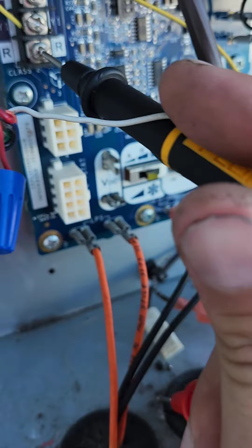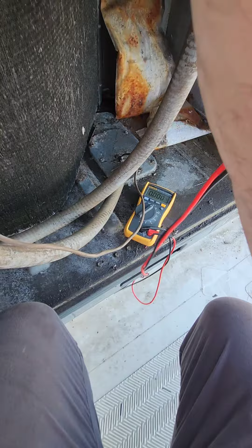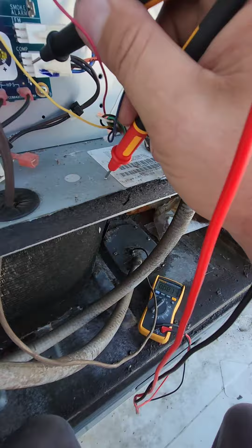Started checking everything else out because there's also smoke sensors and everything you've got to be mindful of in commercial applications. Sometimes you might not have voltage coming back on your cooling call, and it has nothing to do with the unit - it's a duct smoke sensor somewhere in the ductwork you're going to find. There's also troubleshooting airflow issues later on with fire dampers that might be tripped or shut. So always got to be mindful of those things doing commercial.